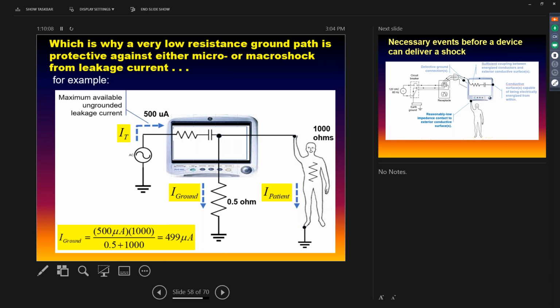If you've got 0.5 ohms of ground resistance versus say 1,000 ohms, which is a low resistance for a human, 1,000 ohms for Joe Person here, Kirchhoff's current law will guarantee that most of that current, 499 out of 500 microamps, is going to flow through the ground. Only a microamp is going to harmlessly flow through the patient. So that same concept, if this is 500 microamps or 5 amps, the concept's exactly the same. Most of that is going to flow through the low impedance pathway as opposed to Joe Person.